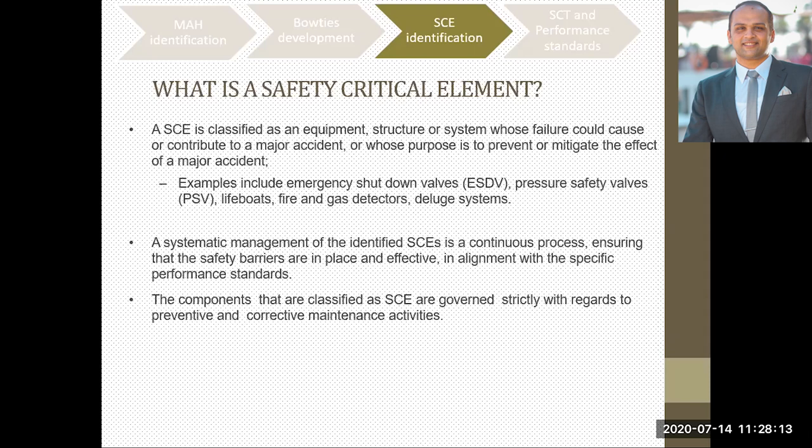The components that are classified as safety critical elements are governed strictly with regard to preventive and corrective maintenance. What is the difference between preventive and corrective maintenance? Preventive is that you have a periodical test. Every year, for example, you test this valve, this pressure safety valve, to make sure it's operating adequately. You test it, it's preventive. Corrective is if it failed to do its job, so we have to do corrective maintenance for it. And it doesn't relate to a specific time. Whenever it's needed, we have to do it.